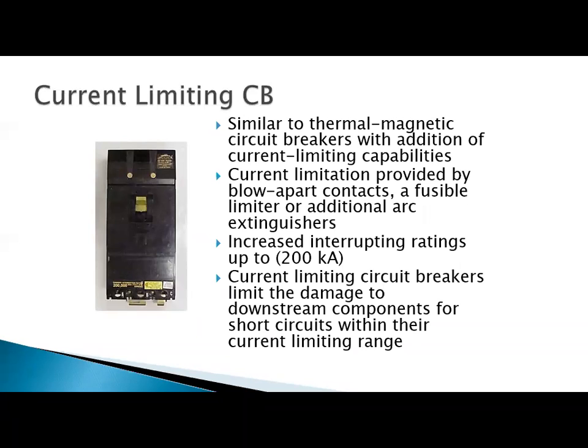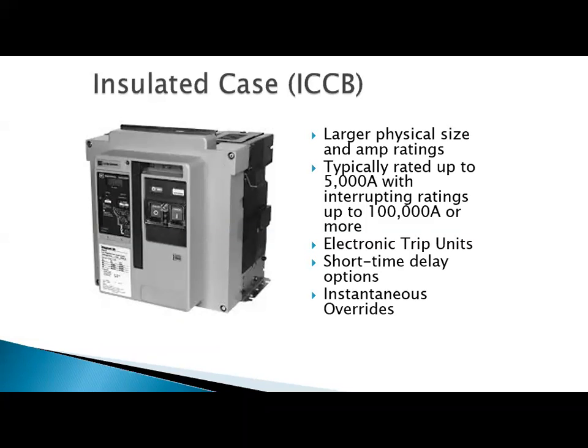So I can adjust the setting on this breaker. That's no problem. Current limiting breakers are going to help limit the amount of fault current that can come through the circuit. Really helps us with arc flash issues. They're going to open the circuit so fast that we're not going to allow the air to ionize and turn into a conductive plasma. What's the difference on these larger breakers that are current limiting? They've got blow apart contacts. They've also got arc extinguishers, where we'll put another coil in there to help suck the arc away from the contacts. And so these breakers are also going to limit damage to any component downstream. Why? Because of their fast clearing time. They're going to help us extremely well with that.